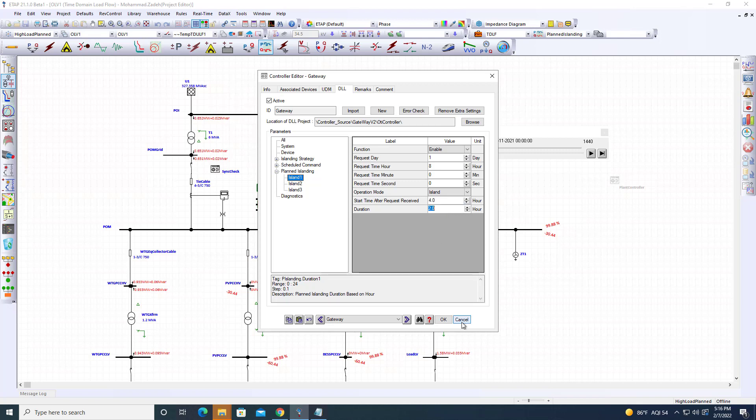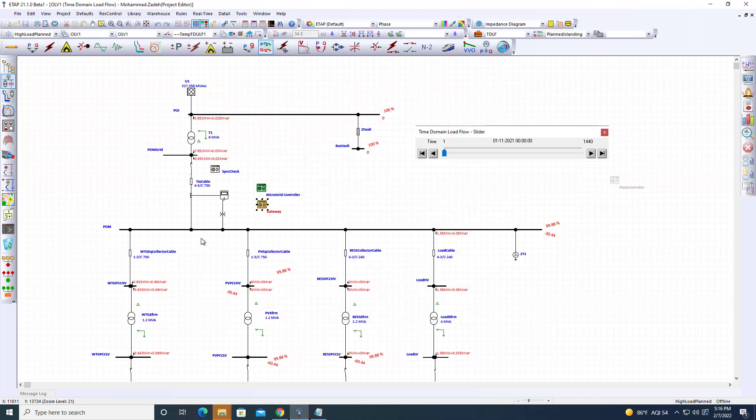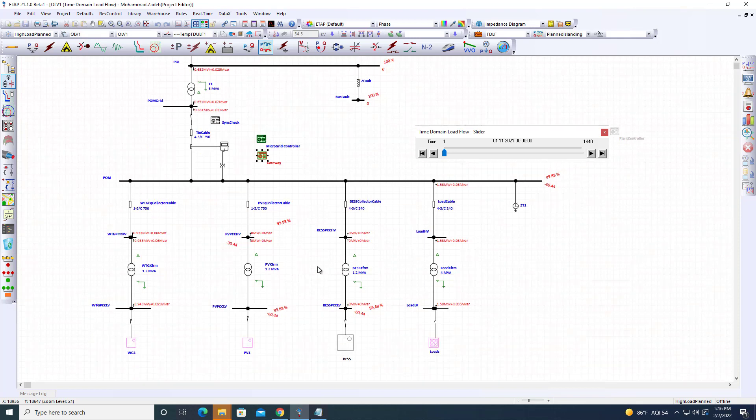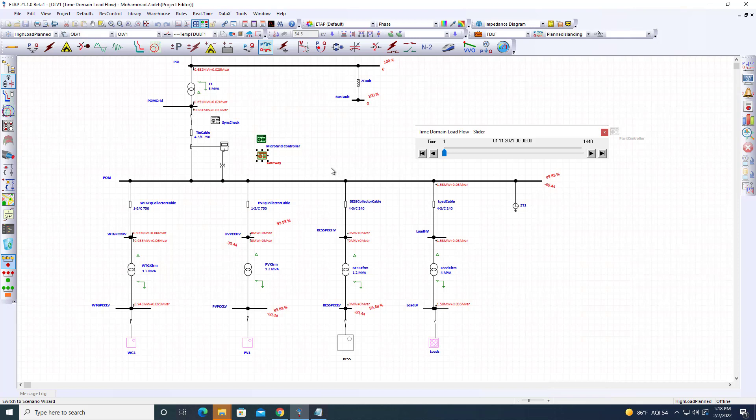The microgrid controller examines load and generation forecasts and battery state of charge. It calculates the battery capacity needed to maintain two hours of islanded operation, determines necessary load shedding, and identifies which assets—such as backup diesel generators—need to be brought online.